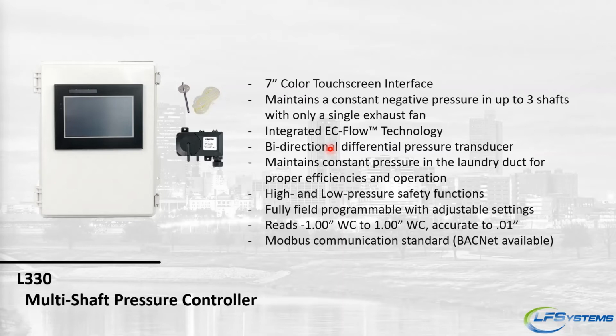And again, we size this based on the operation of the building and your recommendations based on how the building intends to operate. And we select the proper fan and then select the L330 to modulate 1 fan on 3 shafts. Lowers the install cost, and also lowers operational costs because, again, you're not having to maintain 3 products versus that 1. Has all the same features, true bidirectional, high-low safety, Modbus or BACnet. Nice thing is it does come with a 7-inch touchscreen, so now all of that information is on a beautiful interface that the operator or the building engineer can take a look at whenever they need to.